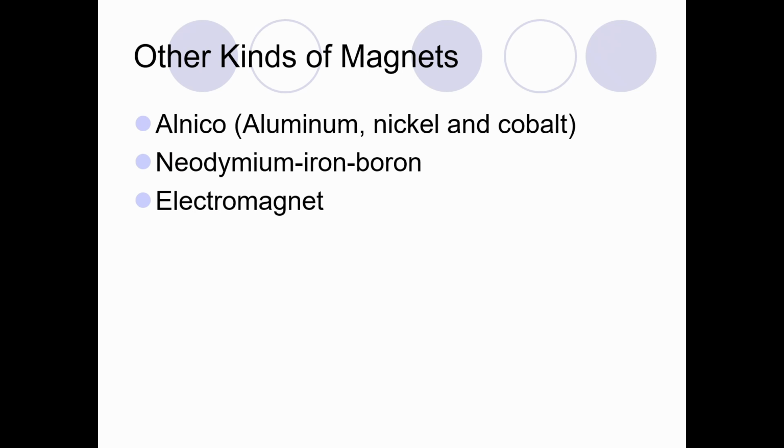The MR department needs a super strong electromagnet that can be turned off for delivery, but once installed, be energized. Once activated, the MR electromagnet cannot be turned off without incurring great expense by quickly dumping the liquid helium.